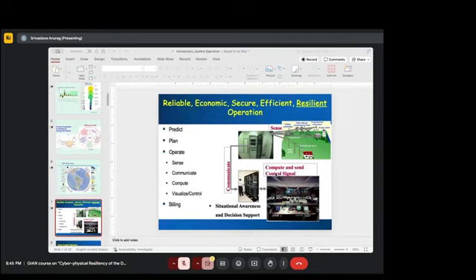You need to aggregate information to do state estimation, which is what even larger distribution grid operators do. When we will get enough sensing to make this work depends on that - we don't even know the network all the way to the secondary houses. The network is typically not known once you leave the transformer, and I'm talking about the secondary transformer which feeds 10 or 4 houses.